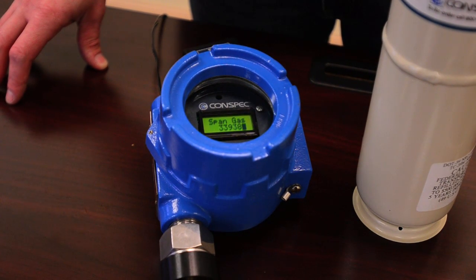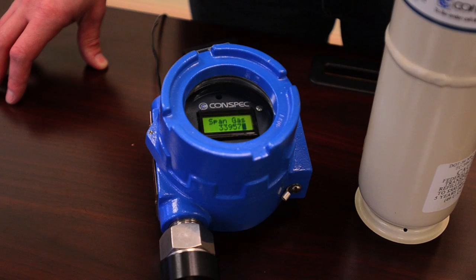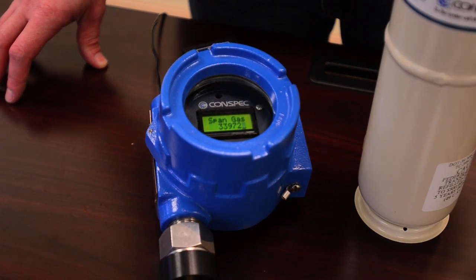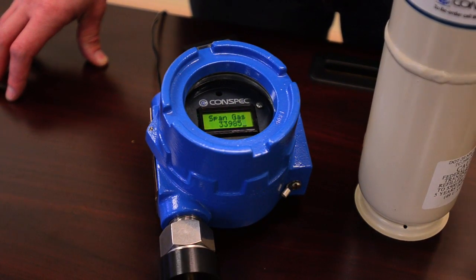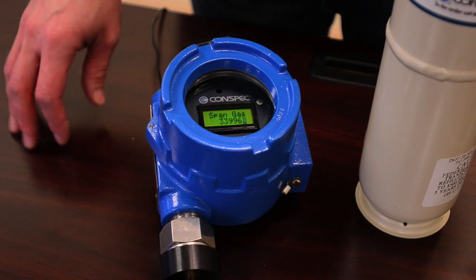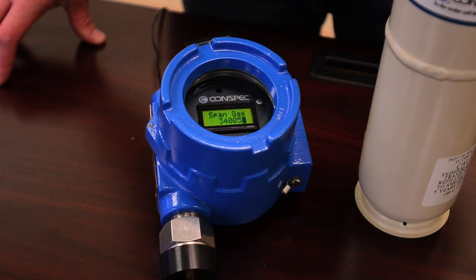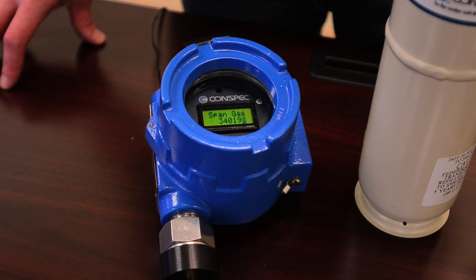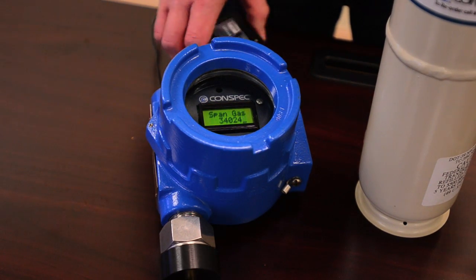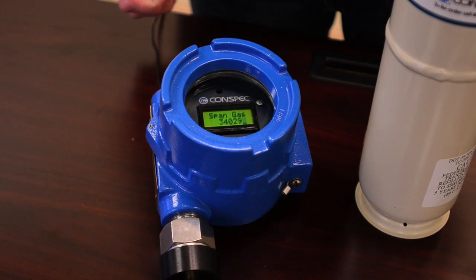Our Universal Series will not allow for bad calibration data to be entered. So if you've accidentally grabbed the wrong gas or you haven't set the programming functions correctly, the monitor will not accept the data and will revert back to the original calibration. So it's a good fail-safe measure.